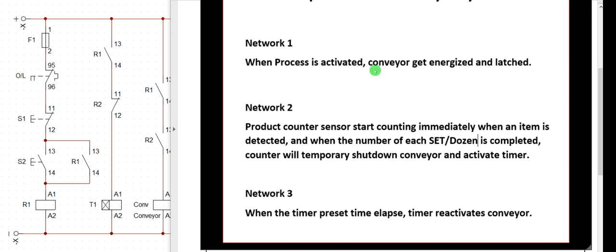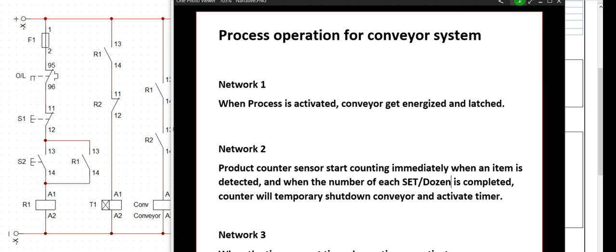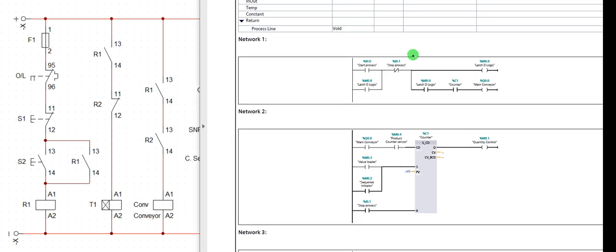The instruction says: when process is activated, conveyor gets energized and latches. So here is our latching circuit. I have my fuse, my overload contact, my stop button, and my start button. I activate my relay R1, which will latch here. The whole of network one from our program logic, if we are converting it to schematic, is going to take care of this logic here.